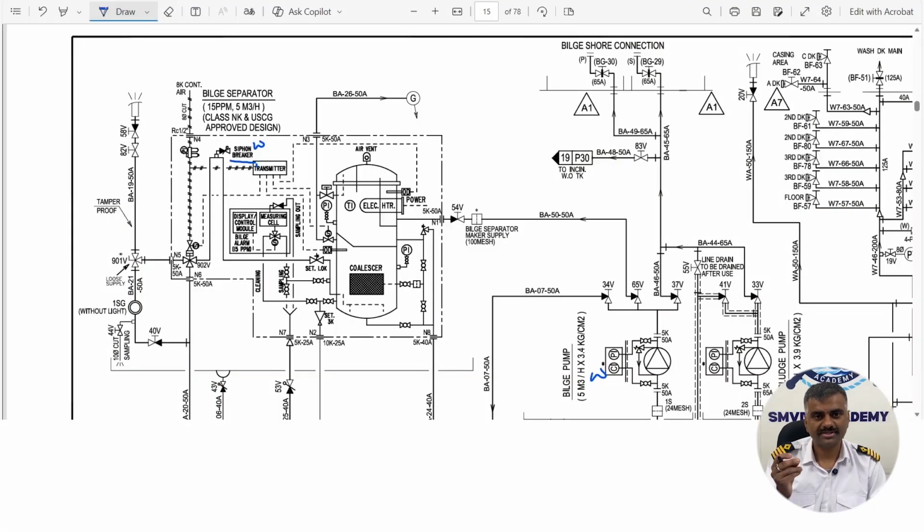Okay, so the concept is just like drinking something from a straw. If you are creating vacuum, fluid flows out from the bottle and comes to your mouth directly when you are sucking it up. So when you pierce a hole in the straw, what will happen? Air will displace the vacuum and the liquid will not come up through the pipe, the straw. So that is the concept of a siphon breaker.